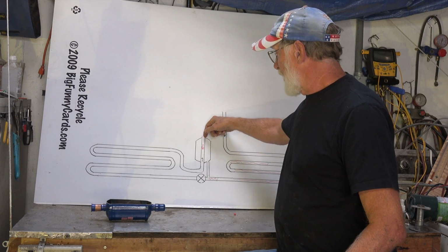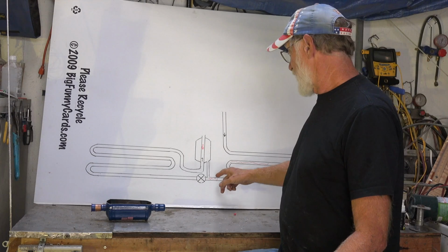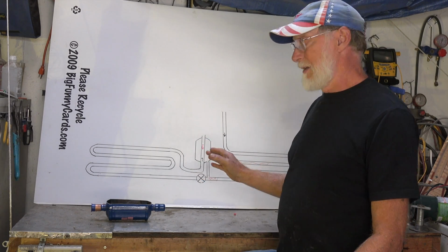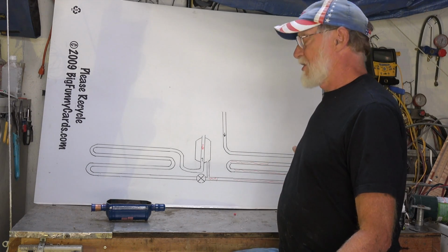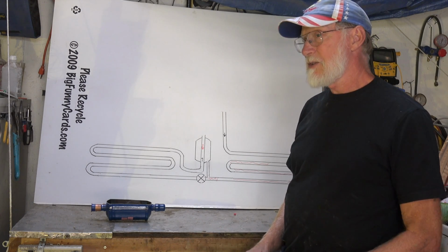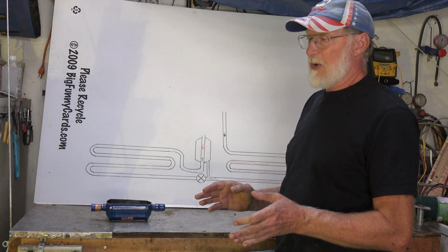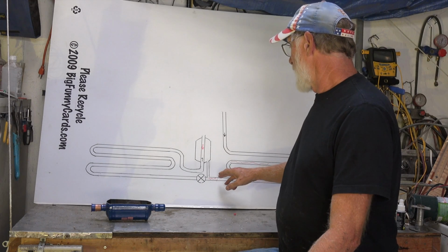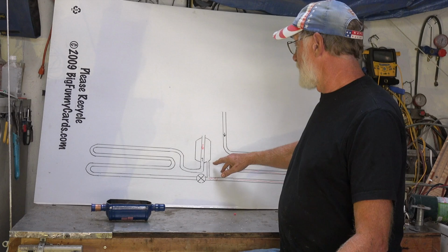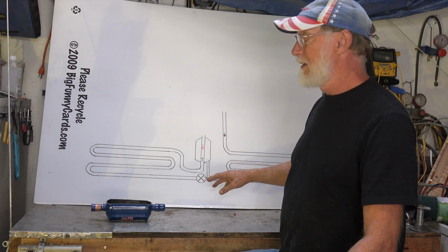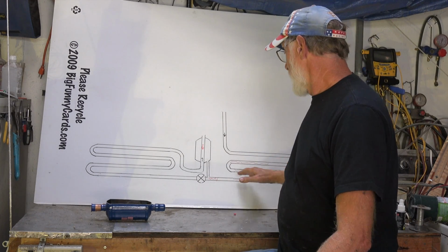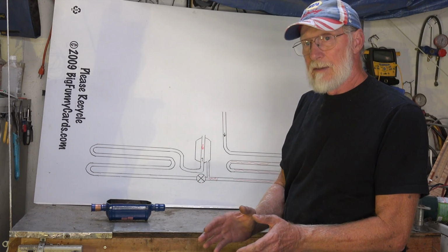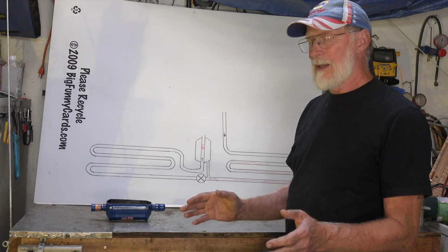Now, if this goes into defrost, this becomes hot gas discharge. This immediately dumps into what is now the evaporator on the inside. There's some concern that dumping the liquid refrigerant in there could slug the compressor. The only ones I've seen these on so far have been scroll compressors, and scroll compressors really don't slug, not like a piston compressor does. So that may be why they use them. Some have said they should maybe have a restriction on the outlet here to feed small amounts of refrigerant in. They don't do that. But that's the difference: they're both storing refrigerant that's not needed at the time they're operating, but they do it in a different manner.